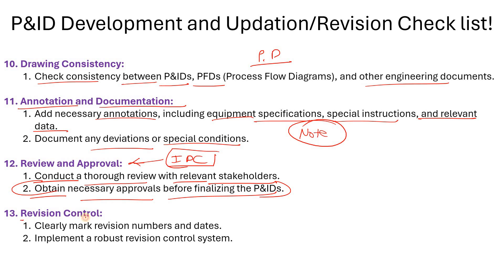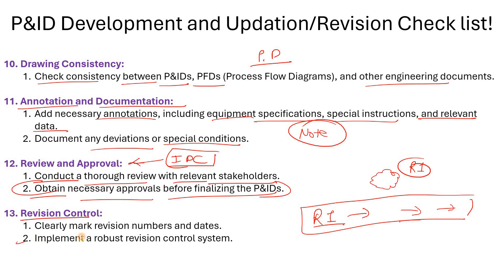Then revision control — clearly mark revision numbers and dates. You can show revisions using a cloud symbol, and write R1, R2, R3 in your title block along with the purpose of the revision, who checked the P&ID, and who approved it. When you prepare a revised P&ID, also send it for review before approval, and review it thoroughly with stakeholders and managers.